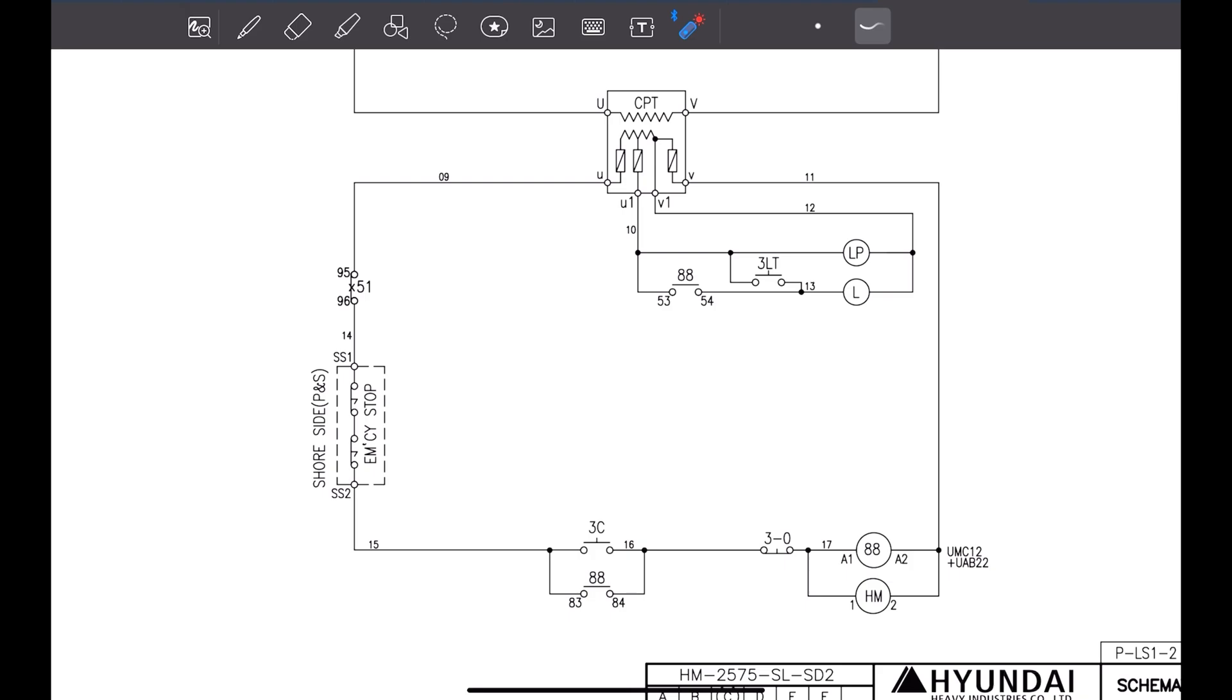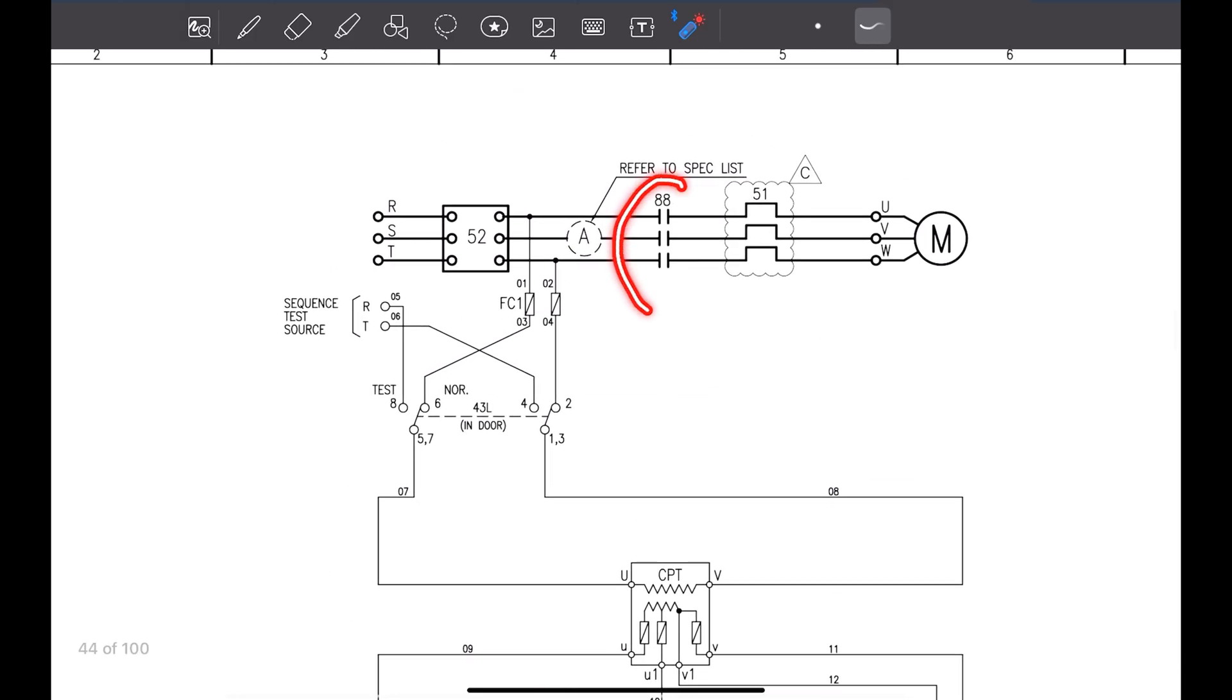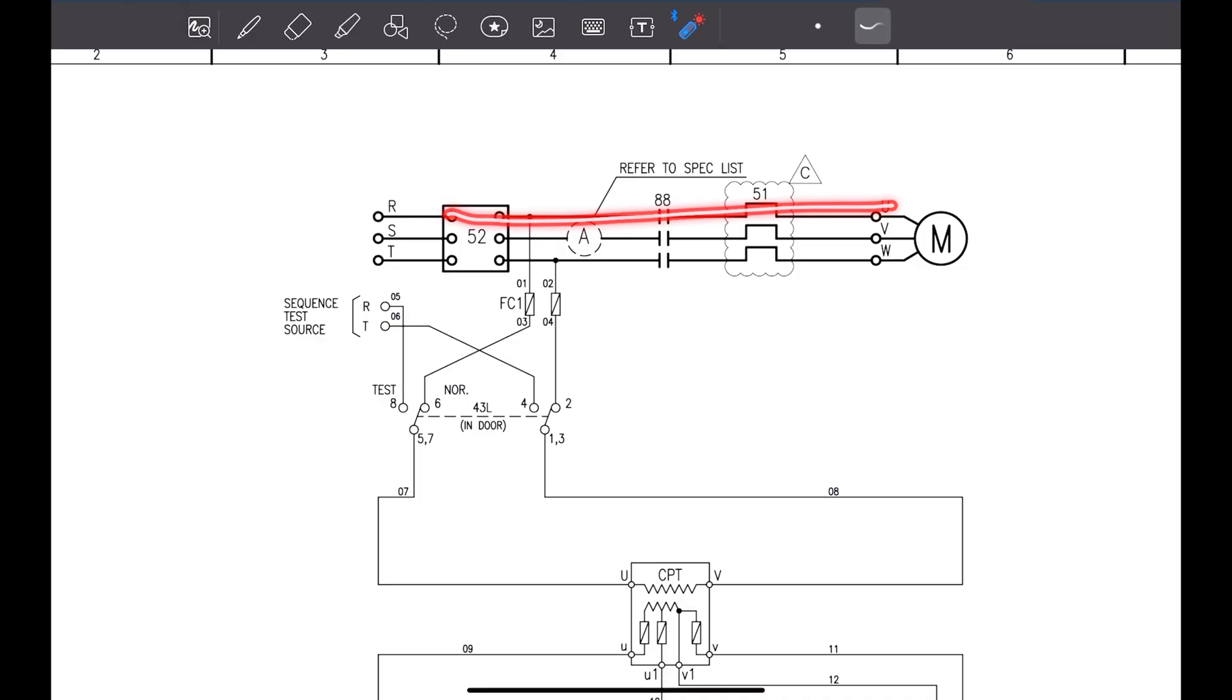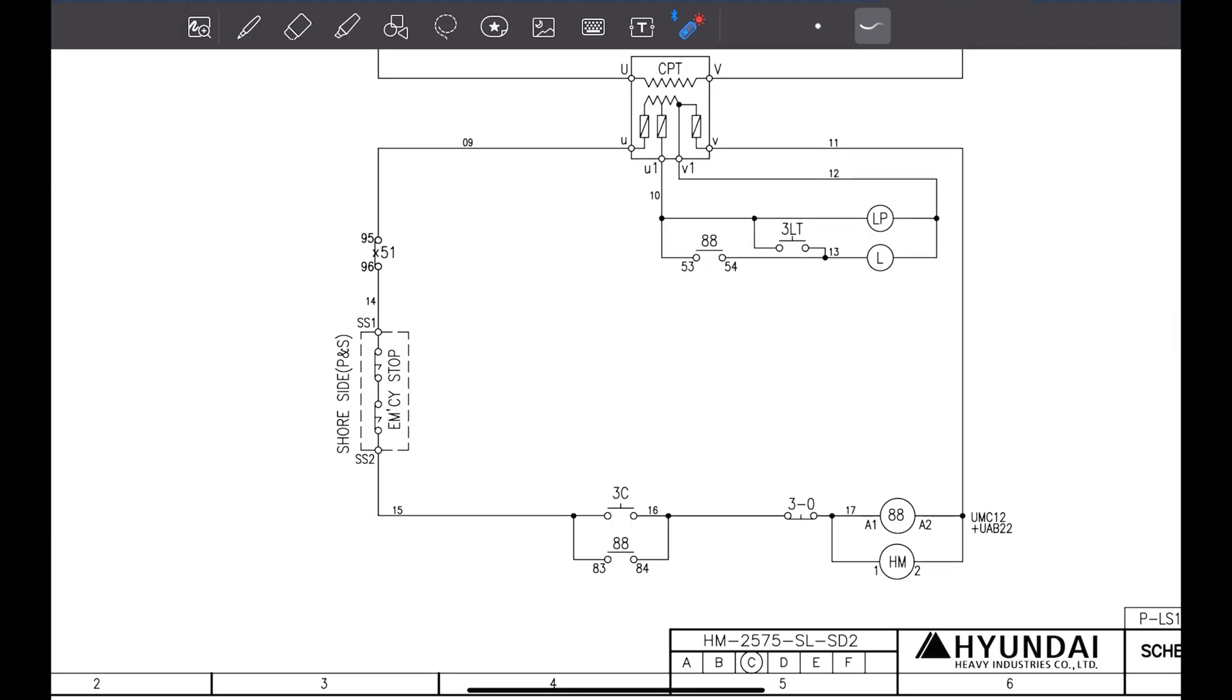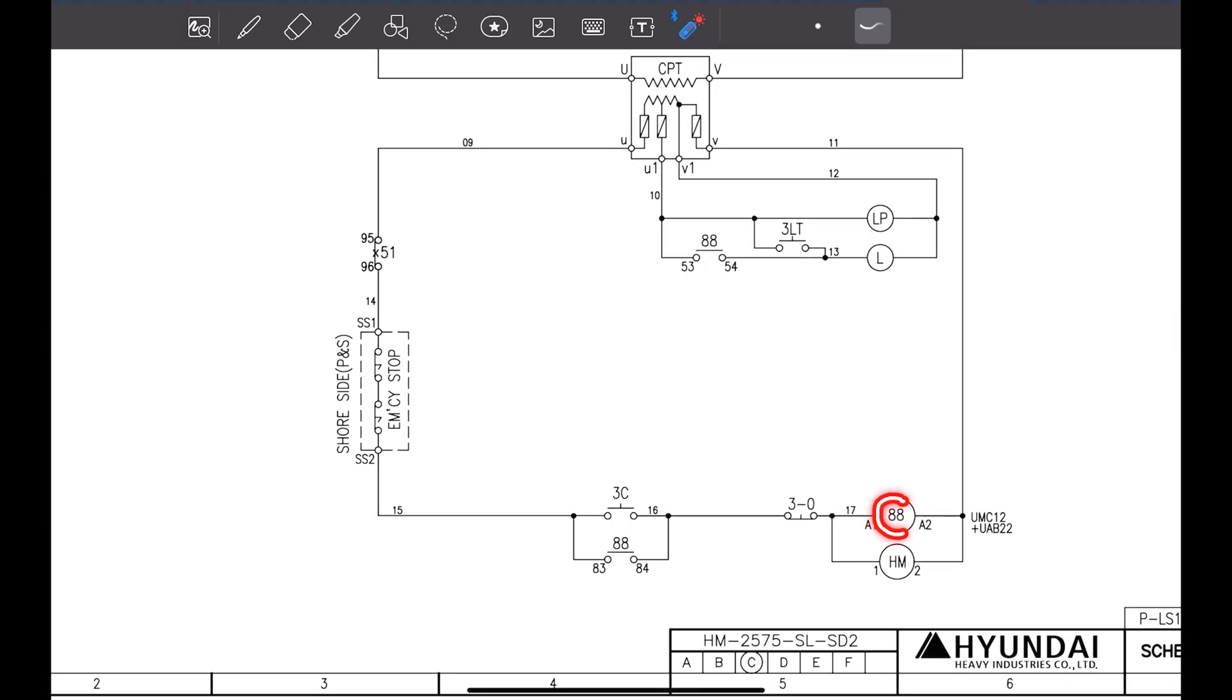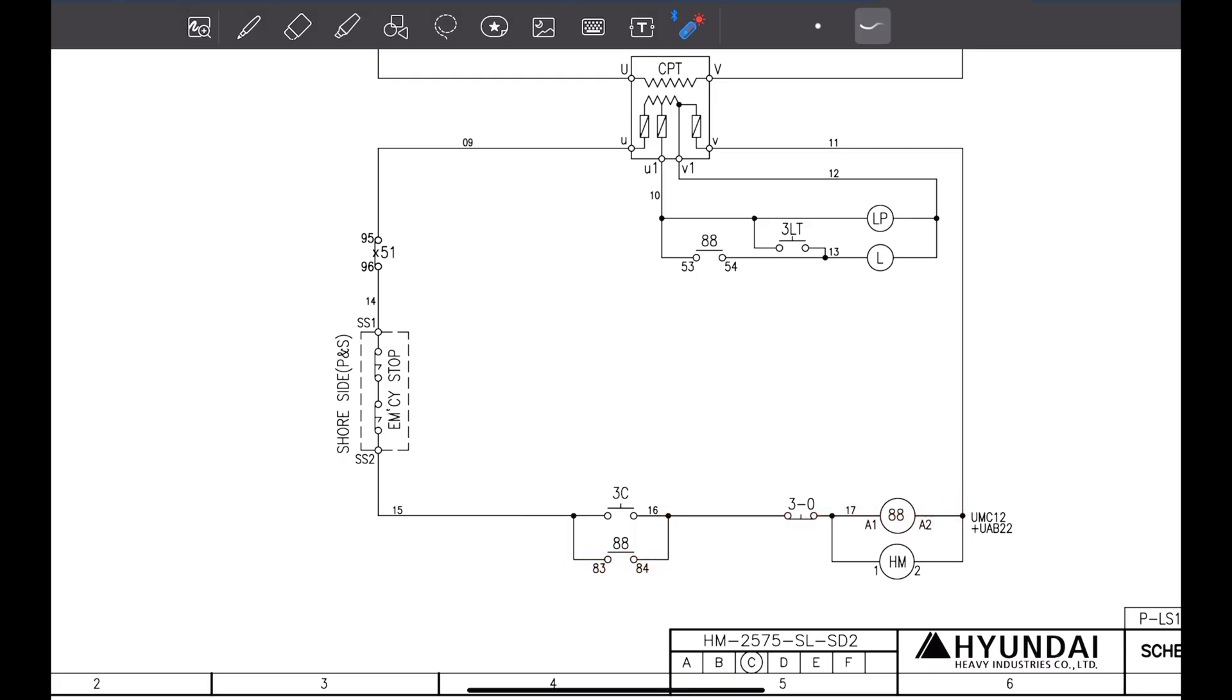As you can see, when we press this button, this is the start button. When we press this button, the 88 will get energized and here 88. This will make and this will complete the circuit for power to transfer. This is how this motor is working. And once this is energized, this 88, this contact, this will close here. This is called latching contact. Because when we are pressing on button, when we are pressing it and again leaving it, then it will go up. For the 88 to remain energized, it will get circuit, it will get current from here and it will get energized.